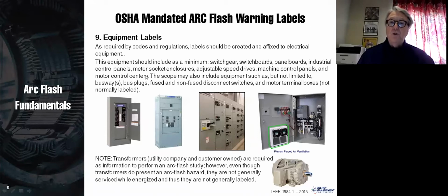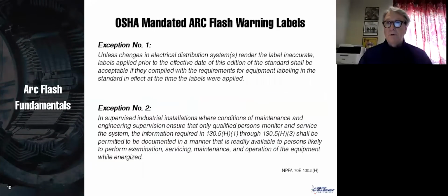Other things you may have labels on depending upon whether you feel that you are going to have to work inside that box or that piece of equipment when it's energized. So things like busways, bus plugs, fused and non-fused disconnect switches, motor terminal boxes, transformers, not typically labeled, but if you want to label them, you're certainly welcome to.